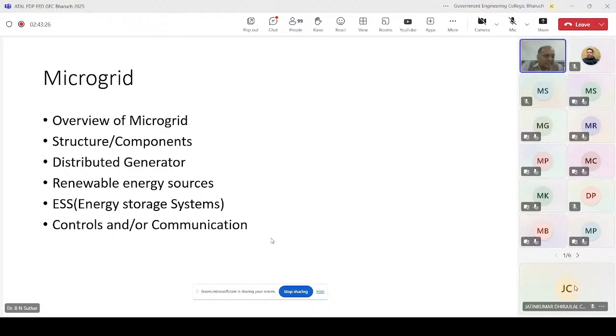Then we should also have control for this particular microgrid. We should be able to control all the RES, ESS, and distributed generators, both conventional and renewable. This can only be controlled if we have a proper communication link between these generators, renewable energy sources, or ESS, along with information about the load and a proper communication network. This can be done using certain interfacing devices, which are also used to interface the microgrid with the grid. Of course, load should always be there in the microgrid.